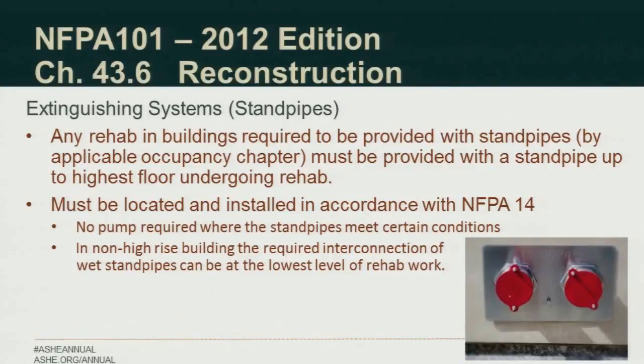I said here, there's no pump required where the standpipe meets certain conditions. Basically, the fire department can provide a certain pressure at that highest point, and you design it to go further when you do the design. And in non-high-rise buildings, the required interconnection of wet standpipes can occur on the rehab floor.